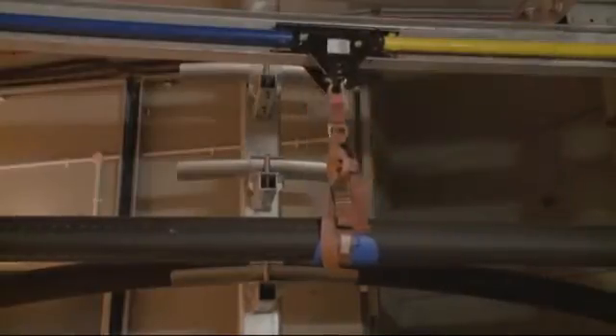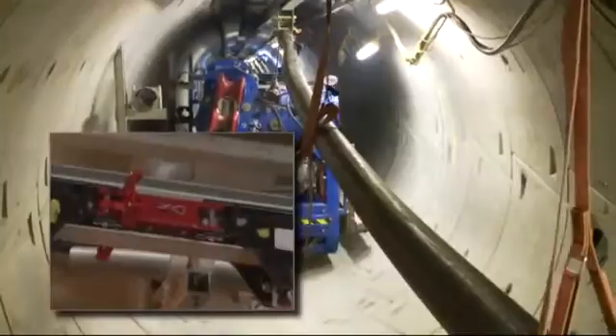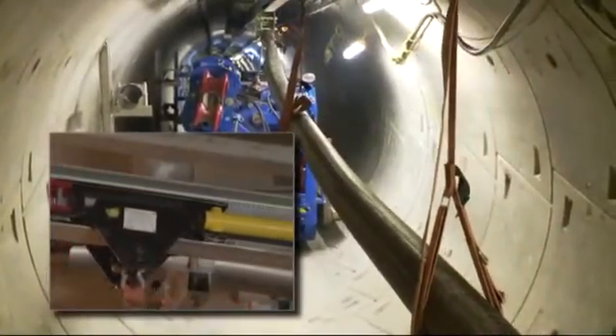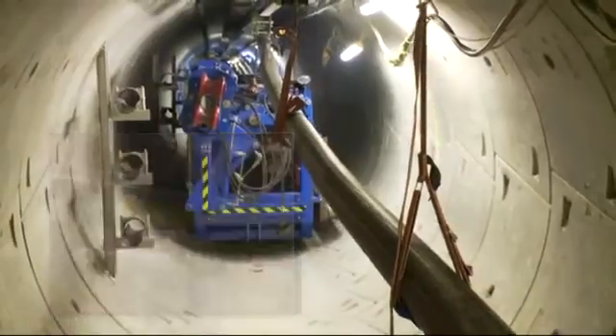The monorail beam is crucial for a number of reasons. First and foremost it ensures that the cable is kept off the invert so we keep the cable clean and that way we can ensure that there's no damage. Secondly the trolley system that we use has an integral braking system. Although the cable pulling machine has emergency measures built in to prevent it from running away, should there be a break in the connection between the rail and the cable pulling machine the trolley will come to an automatic and safe stop.